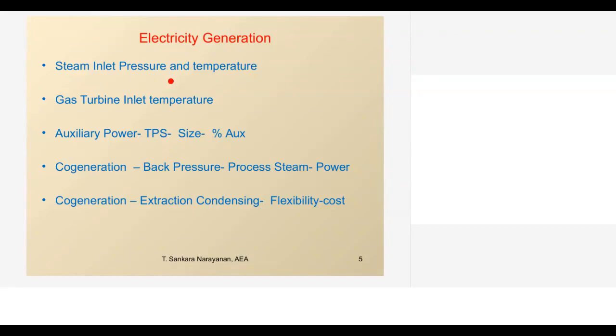the power plant has already decided, when the plant is designed, the steam inlet pressure and temperature. When the steam inlet pressure and temperature are designed by the supplier of the power plant, then the opportunity at the field is only to monitor this and to review where the pressure reduction or temperature reduction is there. Similarly, gas turbine inlet temperature: mostly, if you see, gas turbine inlet temperatures are 1000 to 1100 degrees. There are design aspects where they are planning to increase the temperature up to 1400 or 1500. Mainly, when the gas turbine temperature increases, we need a very good material for the turbine blades. So gas turbine inlet temperature is the guiding factor.